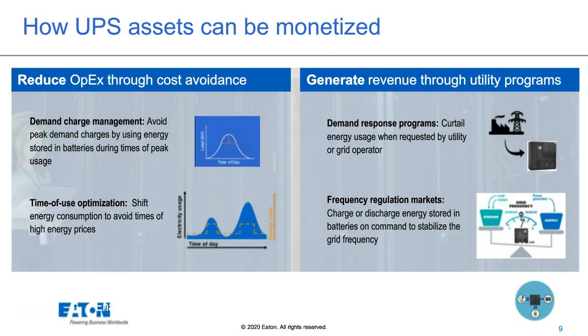If they can avoid those demand charges, if they can avoid setting those peaks on the hottest day of the year or the coldest day of the winter, then they're going to basically positively impact their power charges for the next 12 months. So if I could use a UPS system and its inherent battery for peak shaving, then that would be an ideal capability there that could provide direct monetary benefits.